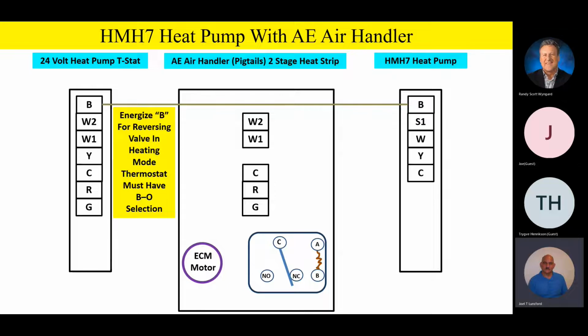Now it's not bad, it's just different. So please remember, on the HMH7 heat pump product, we're going to energize that B terminal from the B terminal on the thermostat for heating mode of operation on the heat pump. So we energize B for heating.